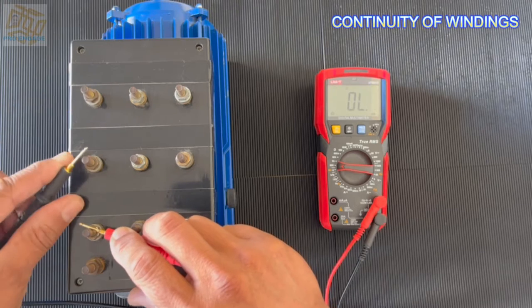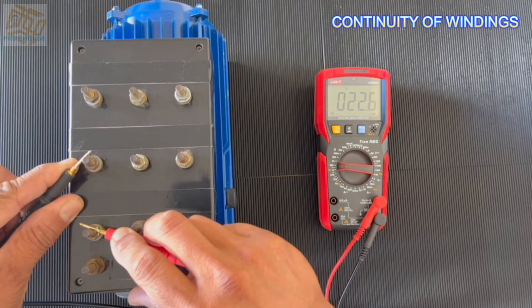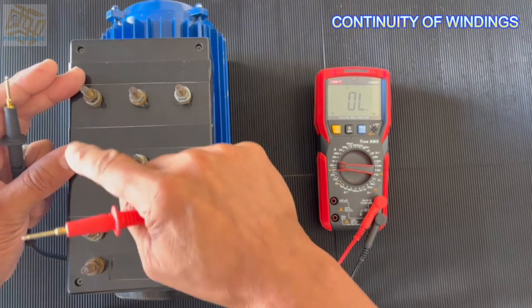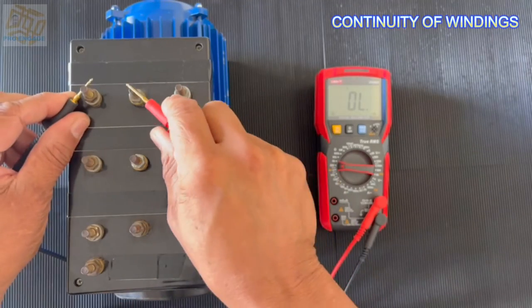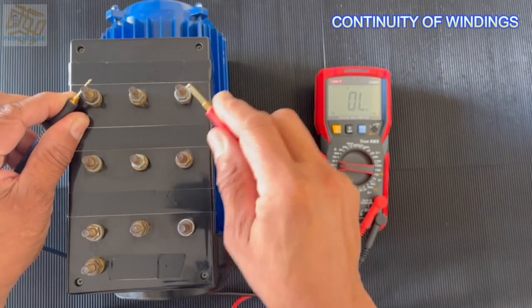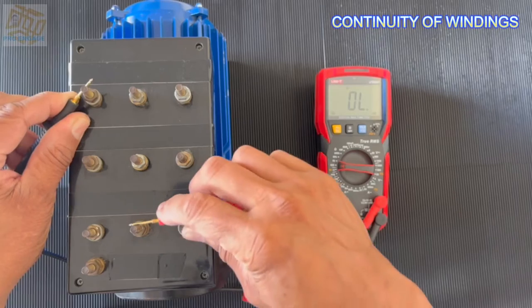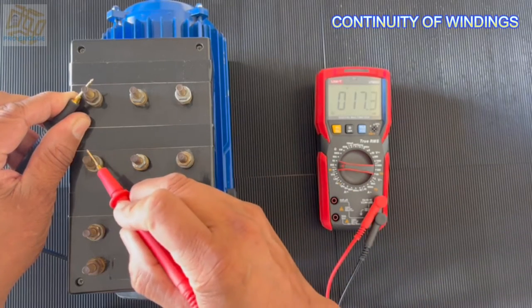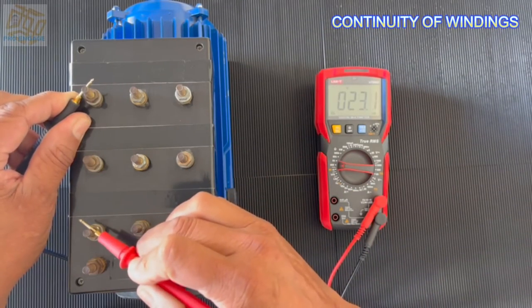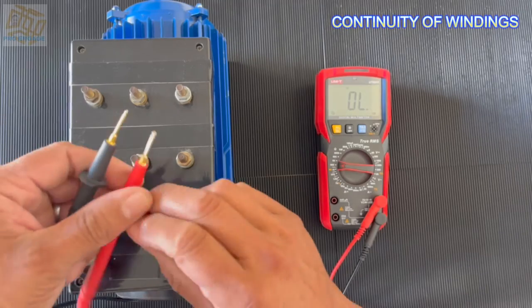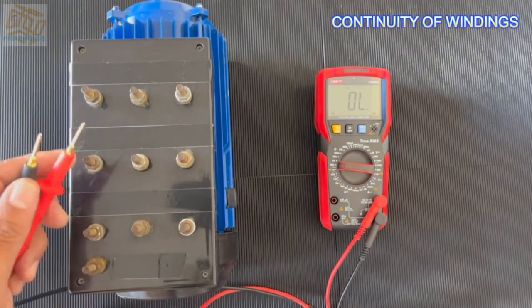Already I found about 17 to 18 ohms, 22.1 and 22.5. So between those points are windings. That tells me it's the rotor because of the slip rings design. I've tested the other points, I've got nothing. And then again I found those, so I have to remember between those points. I'll do a drawing shortly and add that into this video.